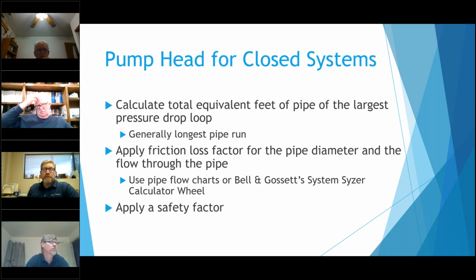But they basically add all this stuff up. Then you have to apply a friction loss factor, and that depends on how much GPM is trying to go through the pipe diameter that you're using. I'm sure there are programs out there. I use B&G's System Syzer wheel. They have a download for it that you can get on your tablet or smartphone, in the Android store or iTunes or what have you. Basically, you say, I've got 3-inch pipe and I'm trying to put 50 GPM through it, and it'll tell you what the friction loss factor is. So you'd apply that to the equivalent pipe length that you came up with.